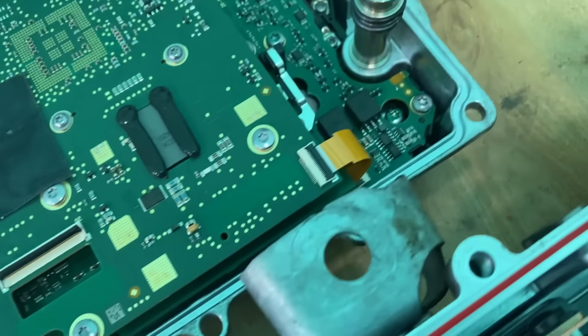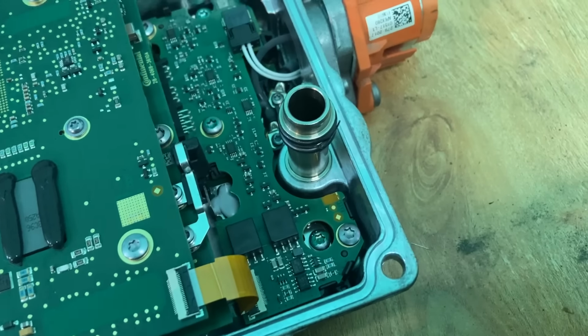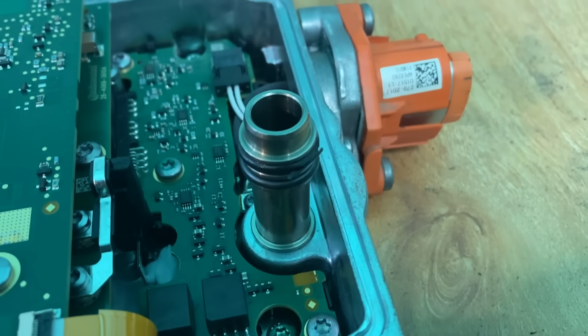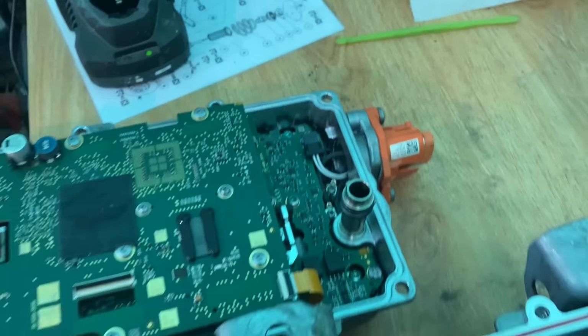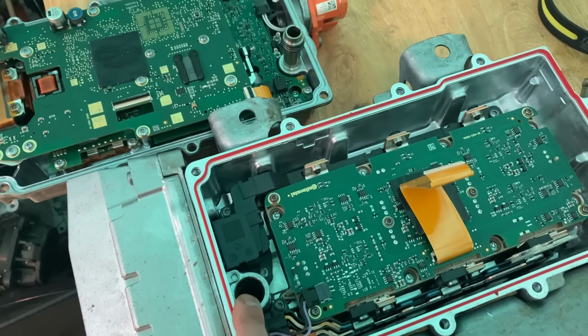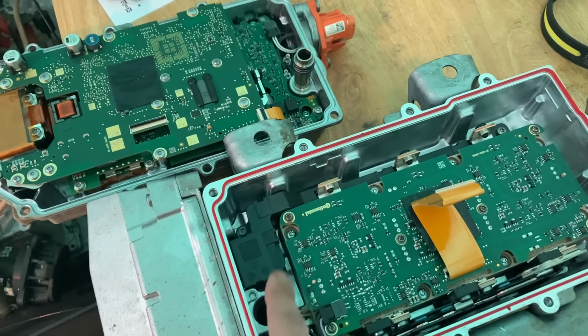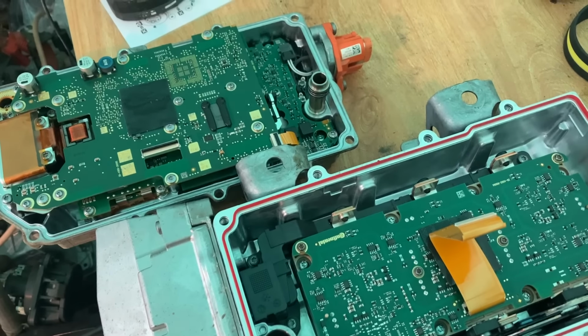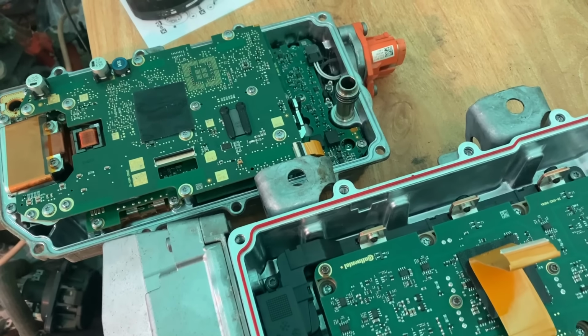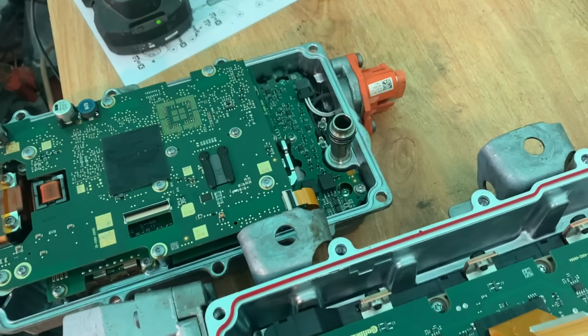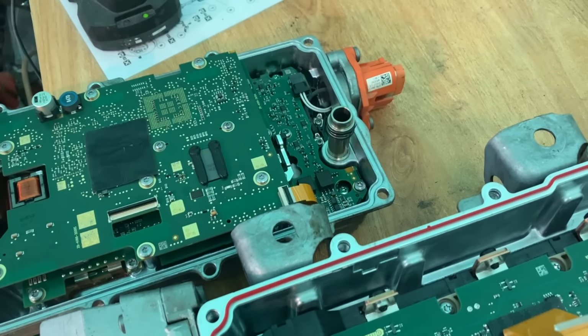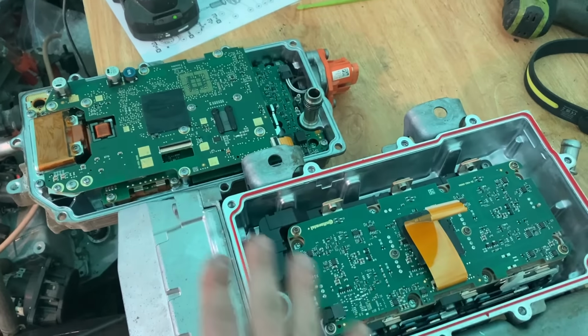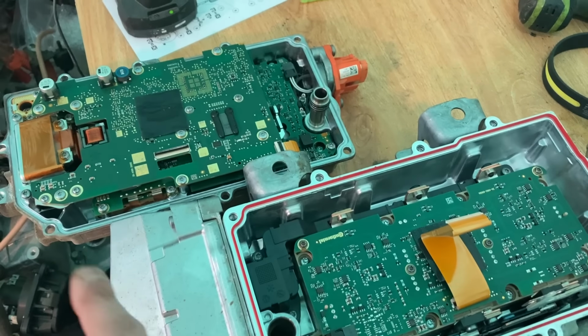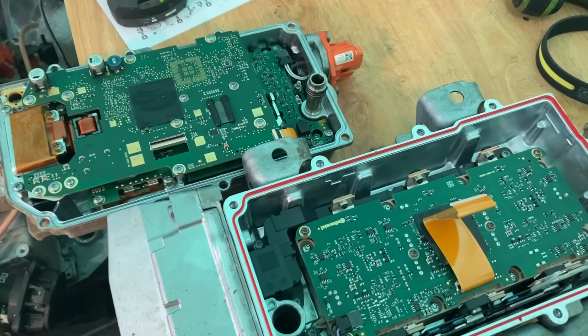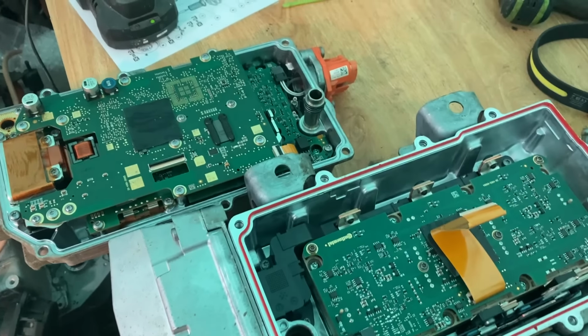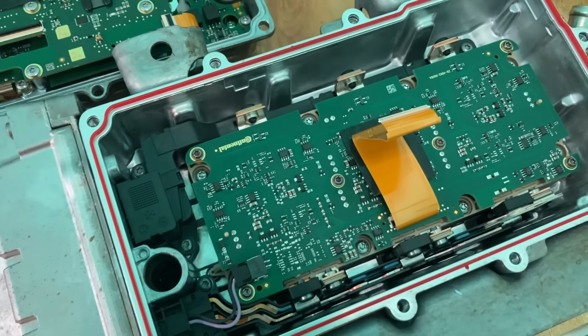The other interesting thing, taking this apart, which you might have spotted if you're eagle-eyed, is this seal. The unit is water cooled and the water actually passes through it, so it's assembled with an internal seal. When you reassemble these, it's obviously a concern whether it might leak again, because we really don't want it filling up with coolant. Oh, and the moisture — there was no moisture inside, by the way, so that was a possible concern from the connector, but that's just a little bit of condensation or water from somewhere. There's no evidence of moisture in here.